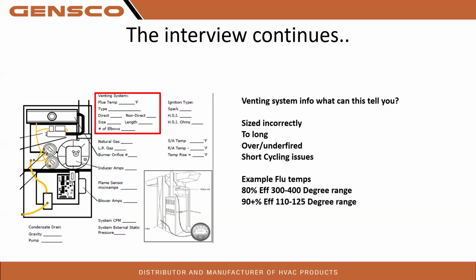So like the S9V2 furnace with a PSC standard flue pipe motor. When you talk about derate for elevation, we don't have a derate kit with a pressure switch like we would with a variable speed inducer motor, because we have a PSC motor. So in a PSC motor, we're going to shorten our flue tables, right? You get up in the 2,000 to 5,000 feet, we're going to allow less pipe, or you're going to have to go to a larger size to get the distance required.